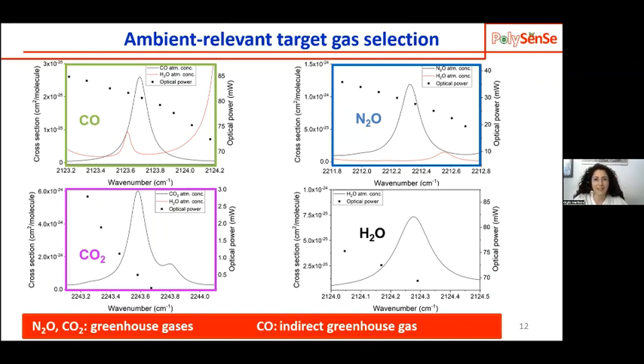environmentally relevant target gases, direct or indirect greenhouse gases, which are carbon monoxide, carbon dioxide, nitrous oxide, and water. Here you can see the simulation of the cross-section of these gases, which is the continuous line, together with the emission power of the laser source. As you can see here, for the CO2, we do not expect to be able to reconstruct completely the absorption feature of CO2 because there's no emission on this side.